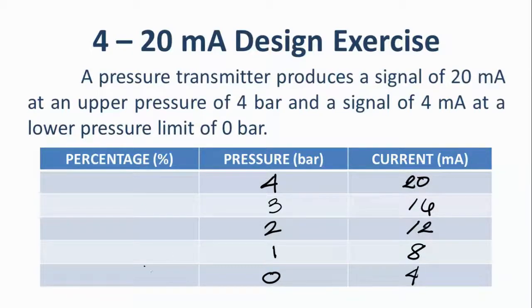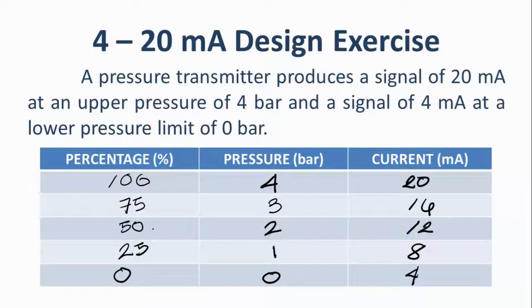For the percentage column, the lower limit is 0% and the upper is 100%. In between we have 50%, and then 25% between 0 and 50, and 75% between 50 and 100. This gives us our complete 5-point calibration: at 0% we have 0 bar and 4 mA; at 25%, 1 bar and 8 mA; at 50%, 2 bar and 12 mA; at 75%, 3 bar and 16 mA; at 100%, 4 bar and 20 mA.